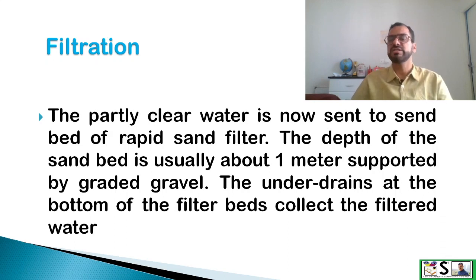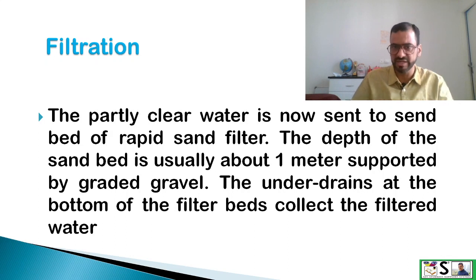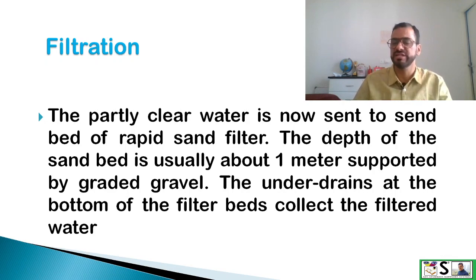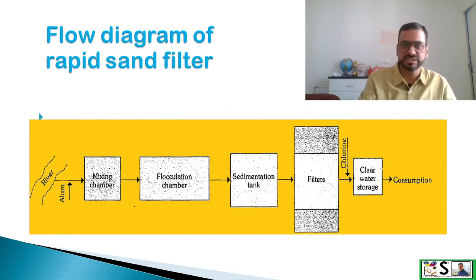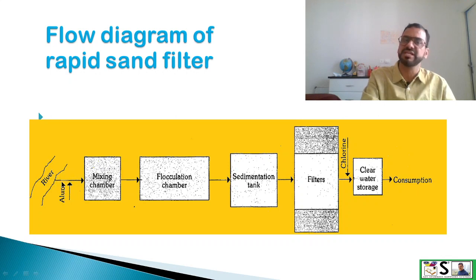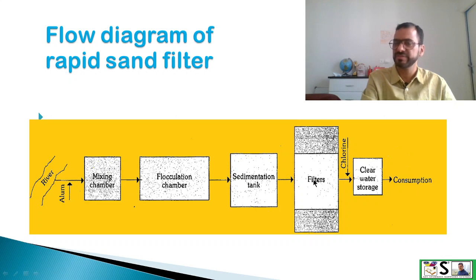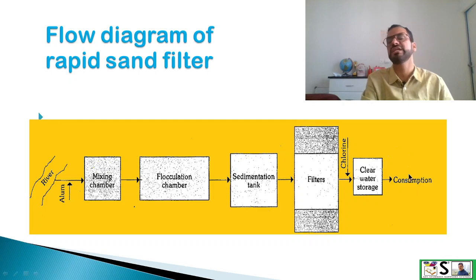The partially clear water is sent to the sand beds of the rapid sand filter. The depth of sand is usually 1 meter supported by graded gravel, with an under-drainage pipe system below to collect filtered water. In the flow diagram: water source → mixing chamber (alum added) → flocculation chamber → sedimentation tanks → filter bed → chlorine addition (disinfection) → clear water storage reservoir → distribution for consumption.